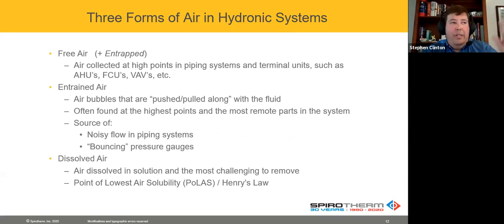Invariably, you get little pockets up and down where water gets caught. Now, when the pumps start, those air bubbles are pushed along. They stay in the coils, they stay in the high points. The other bubbles start being pushed throughout the system. Oftentimes they end up at the highest points, penthouse mechanical rooms, air handling units and mechanical rooms at the furthest end of the system. You have noisy flow, you have bouncing pressure gauges.